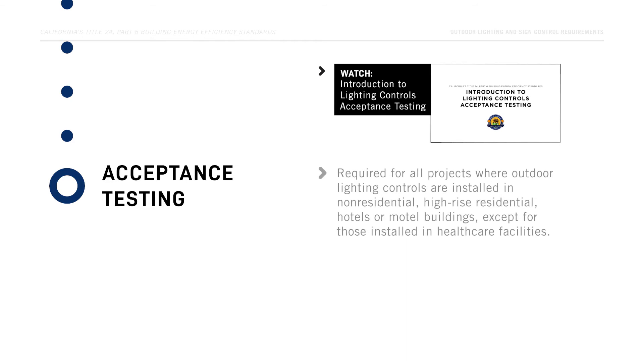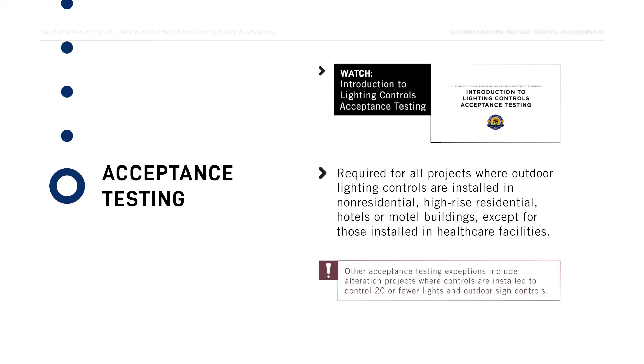To comply with the Energy Code, acceptance testing is required for all projects where outdoor lighting controls are installed in non-residential, high-rise residential, hotels, or motel buildings, except for those installed in healthcare facilities. Other acceptance testing exceptions include alteration projects where controls are installed to control 20 or fewer lights, and outdoor sign controls.